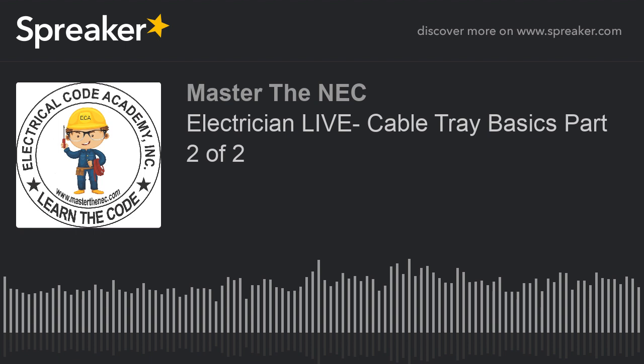All right, so you're saying, what, Paul, why didn't it send me back to 310.16? Well, this is a beautiful thing here. If it's 600 and larger and you install them based on those sizes in 392.22(B), and it's an uncovered cable tray, then I am going to limit the ampacity to 75% of 310.17.